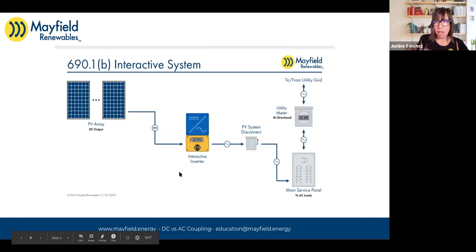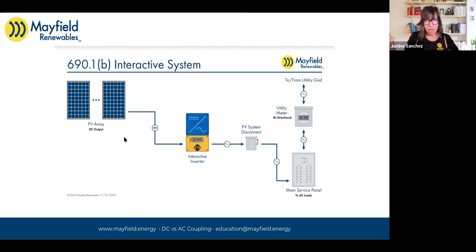And those installers and designers that are on the call are very familiar with the idea that your PV array might be much bigger in DC capacity than your interactive inverter can process. It's called a higher DC to AC ratio. And so designers have been doing this for years. They realize that when the sun's shining and it's daytime, it's a bit warmer, maybe we don't have perfect conditions to produce the entire capacity that this array is actually able to produce. And so they downsize the inverter because in a lot of cases, they're not going to be able to utilize that extra kilowatt capacity of the array that it can produce under laboratory conditions.